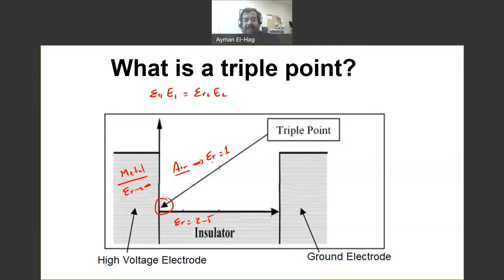Now, when you come to a material like air, this is equal to 1. When you come to material like the insulation or the conductor, this is much higher than 1 for the conductor and 2 to 5. Then what will happen here? The electric field in the air will be much higher than the electric field in the insulating material. So, this will lead to enhancement of the electric field.